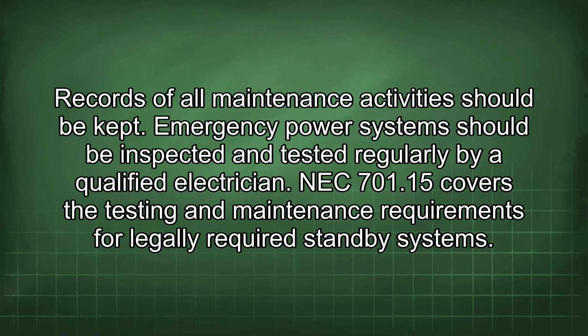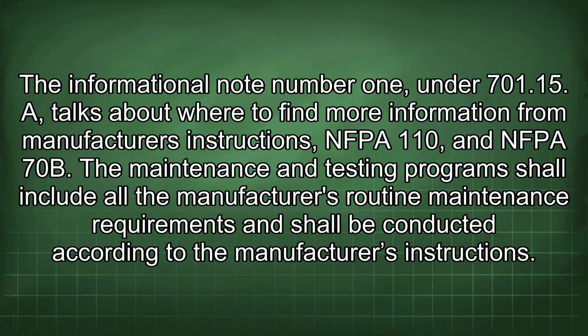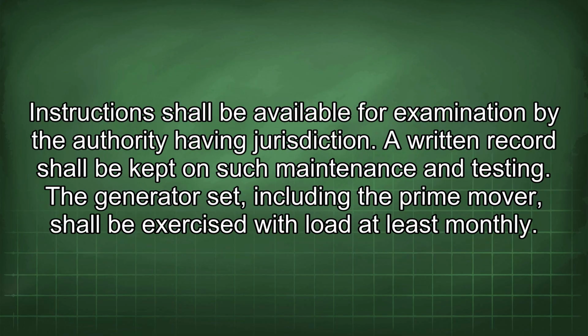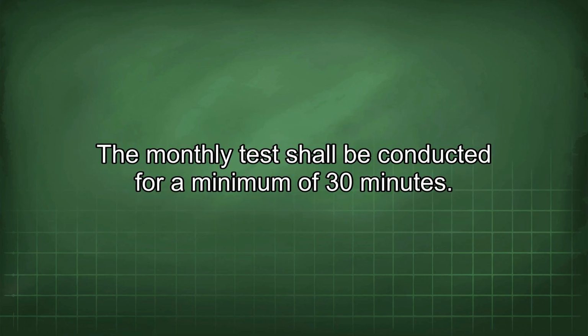NEC 701.15 covers the testing and maintenance requirements for legally required standby systems. The informational note number 1 under 701.15.A talks about where to find more information from manufacturer's instructions, NFPA 110 and NFPA 70B. The maintenance and testing programs shall include all the manufacturer's routine maintenance requirements and shall be conducted according to the manufacturer's instructions. Instructions shall be available for examination by the authority having jurisdiction. A written record shall be kept on such maintenance and testing. The generator set, including the prime mover, shall be exercised with load at least monthly. The monthly test shall be conducted for a minimum of 30 minutes.